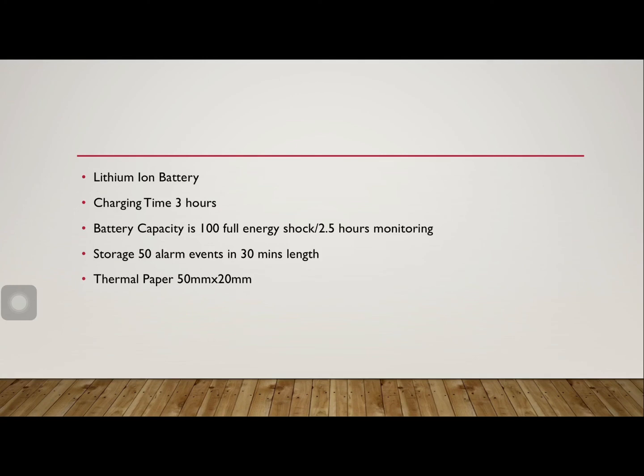So, the battery is lithium-ion. Charging time is 3 hours. Battery capacity is 100 full energy shock, or 2.5 hours monitoring. So we have the storage of 50 alarm events in 30 minutes length, and the thermal paper is 50 mm by 20 mm.